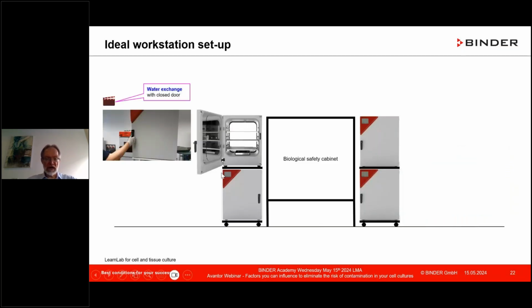Then the water exchange. All of us know the gold standard, as you see in this picture right here, upper left-hand side - here you have the water pan. You also have possibilities with an external water pan, using, for example, steam humidification, and you don't have to open the glass door to exchange the water as you would with the water pan. Here you have a bag, for example, and that is done within seconds. The door remains closed, so reducing the risk of contamination. The conditions inside are stable, you're not interrupting them. And that's also something, if you have very sensitive, valuable specimens, that would be something to consider.